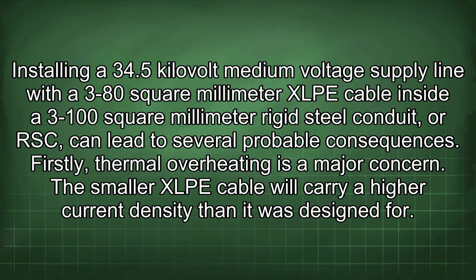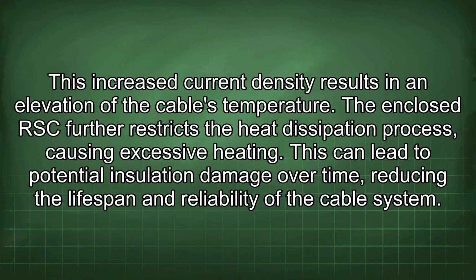Installing a 34.5 kV medium voltage supply line with a 3-80 square mm XLPE cable inside a 3-100 square mm rigid steel conduit, or RSC, can lead to several probable consequences. Firstly, thermal overheating is a major concern. The smaller XLPE cable will carry a higher current density than it was designed for. This increased current density results in an elevation of the cable's temperature. The enclosed RSC further restricts the heat dissipation process, causing excessive heating. This can lead to potential insulation damage over time, reducing the lifespan and reliability of the cable system.